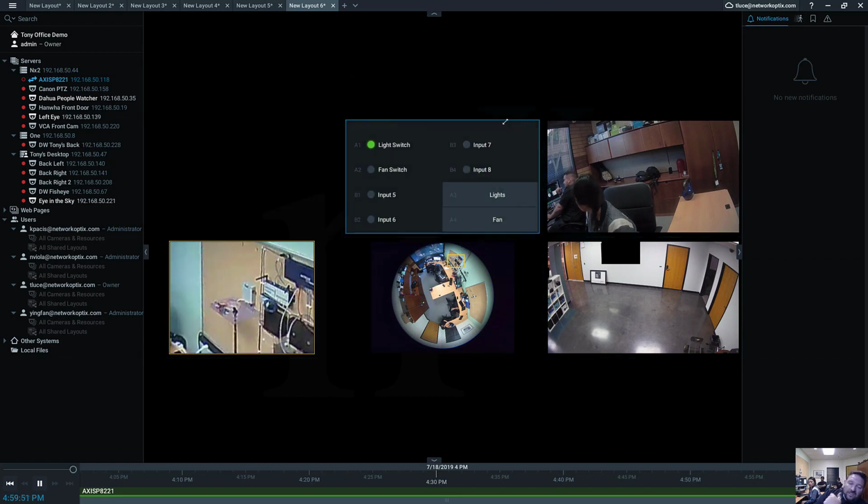No. The toughest part about IO, I'll be honest, is doing the hardwire to the external stuff. That's where you've got to know the voltage and what you're connecting to and all that kind of good stuff. Well, once you've connected an IO, though, you can create rules.